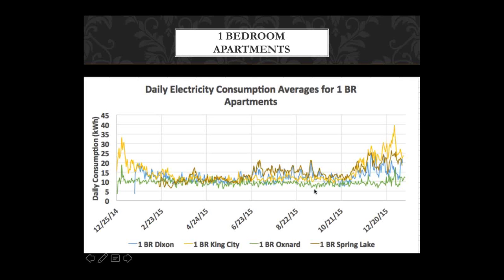Interesting thing to know: the brown line stays higher than the blue line a lot of the time, and that's because their domestic hot water tank's thermostat was not in the water. So we discovered from monitoring that all 61 water tanks at Spring Lake, the brown color, were broken essentially. They were running at 135 degrees 24/7, which is why the energy consumption never drops like it should compared to the blue. For me, I came to understand how important it is to meter things to catch large construction failures.